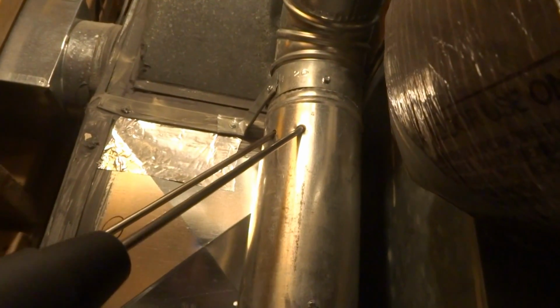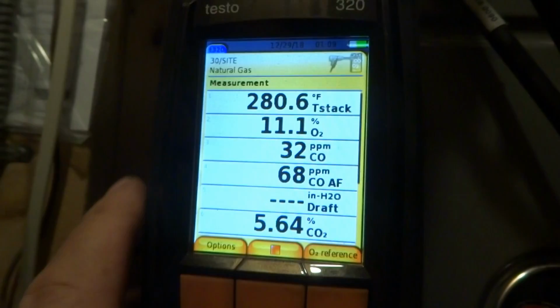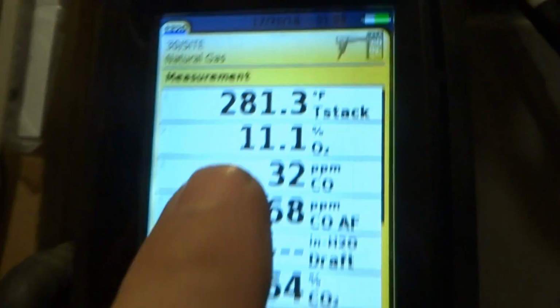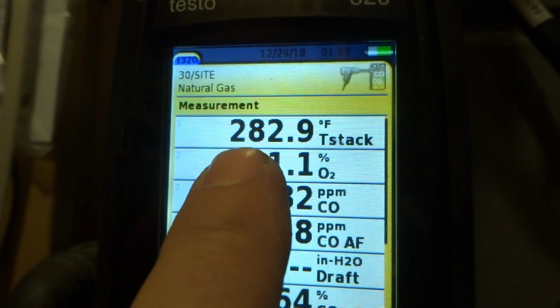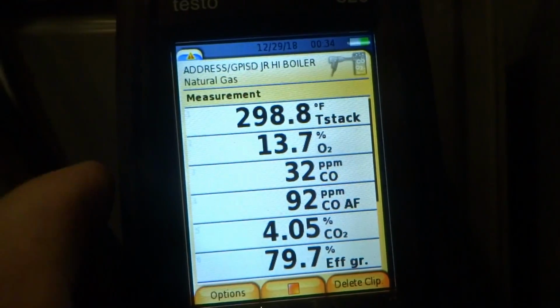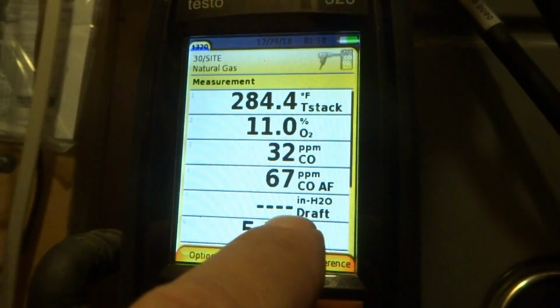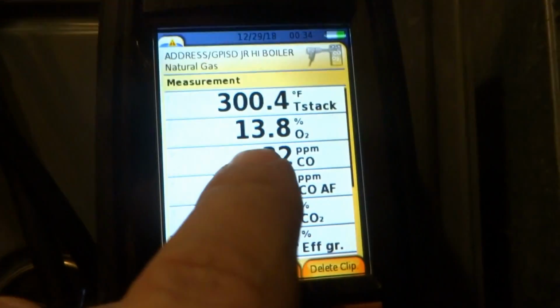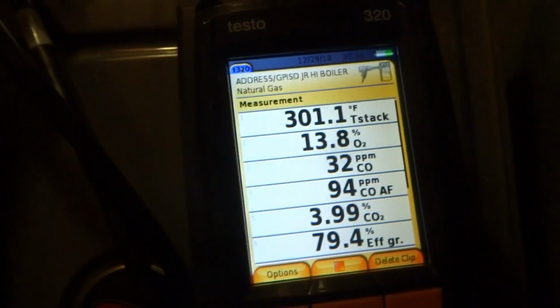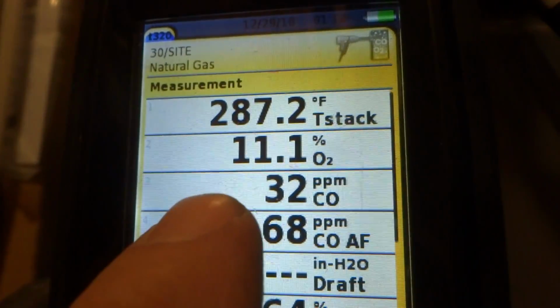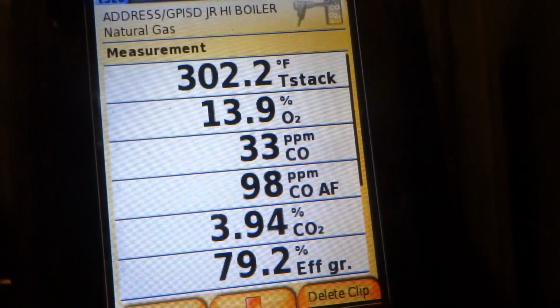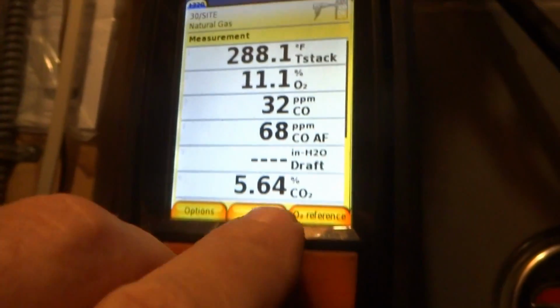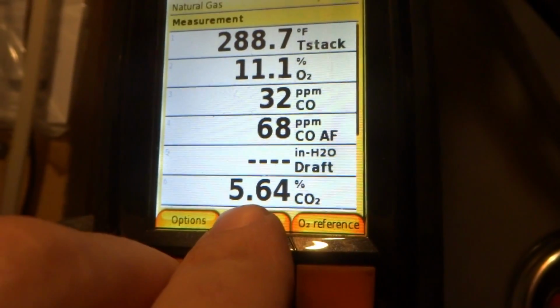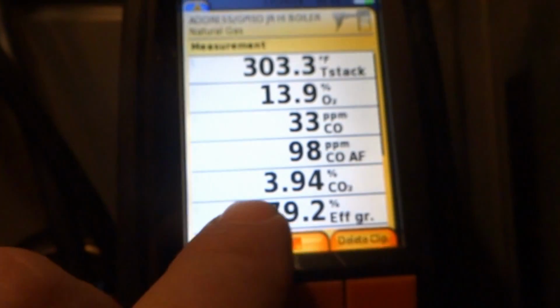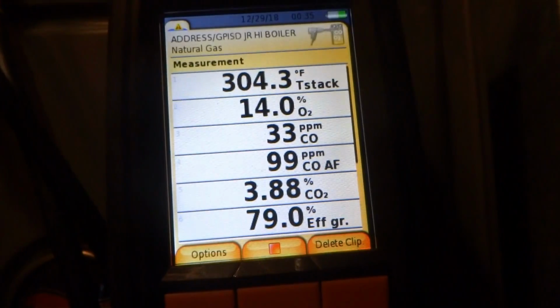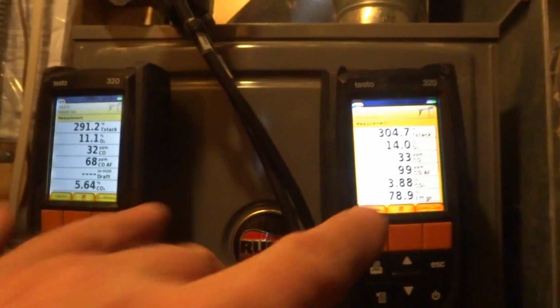I got both probes going in the same spot, right? Alright guys, so this is number 1, the one I usually use. You see the stack temperature, 282. This one is 298, which is pretty close, within reason. The oxygen, the O2, is 11. This one's 13.8 - within a couple. The ppms is 32 and 32, so that's good. And then the CO2 is 5.64, and this one is about 4. They are off a little bit, but I'm gonna print these two.